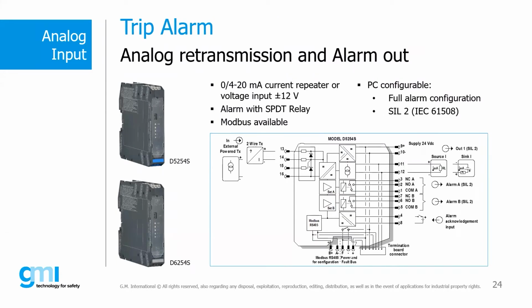We also have a unit with trip alarm, so one unit that can be used as a 4 to 20 milliamp retransmission to the systems, and also has 2 relays. The relays can be used for trip alarm, that's active, for low alarm, high alarm, mid alarm, different alarms that are also PC configurable, and the alarms, the output, and the range also, of course. And it's available with the SIL 2 certification. Also in this case, we have a solution for IS and non-IS applications.